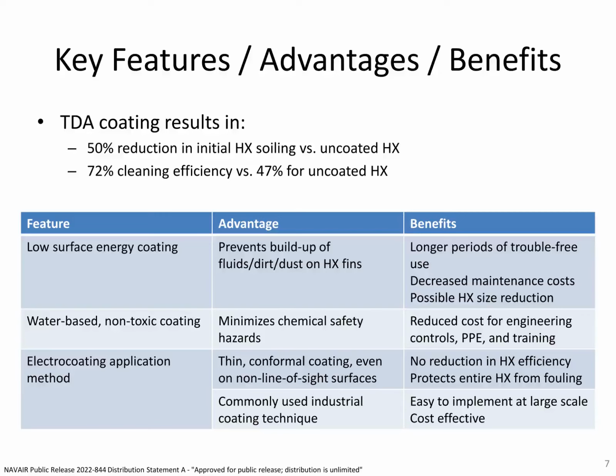A key feature of our coating is the low surface energy, which prevents buildup of fluids, dust, and dirt on the heat exchanger fins. This results in longer periods of trouble-free use, decreased maintenance costs, and could even allow for heat exchanger size reductions. The coating is water-based and non-toxic, which minimizes the chemical safety hazards, thus reducing costs for engineering controls, PPE, and training.